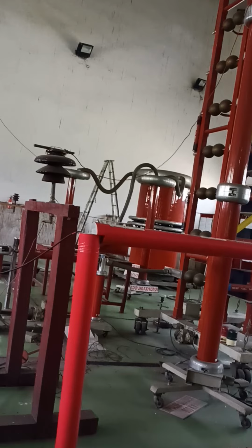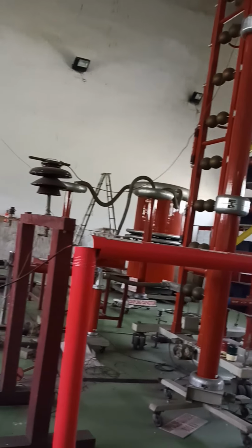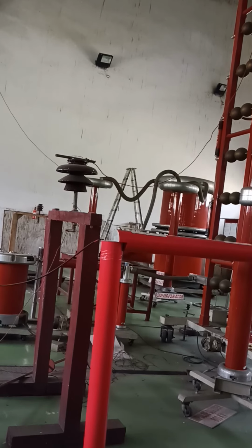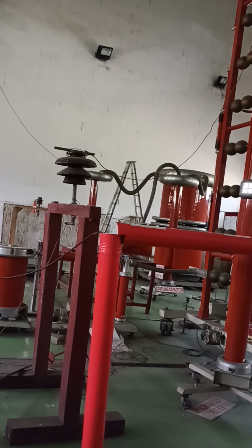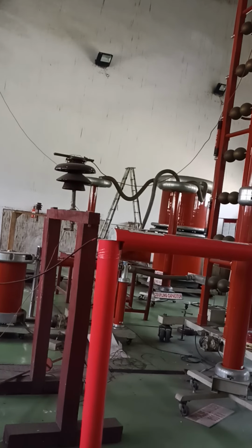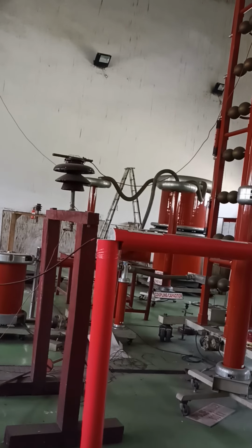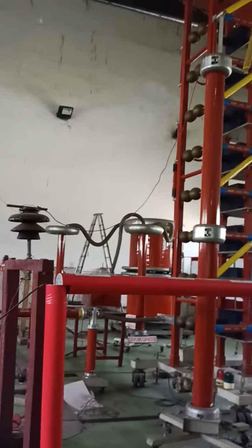But in the case of 300 kV at 50 hertz, and this is DC also. Here it is AC. So for 50 hertz, 300 kV, the resistance loss will be very high. So what we are doing is using capacitive dividers, with capacitors connected in parallel. So it will be just like a resistance only. Resistance in series, and capacitors in parallel.